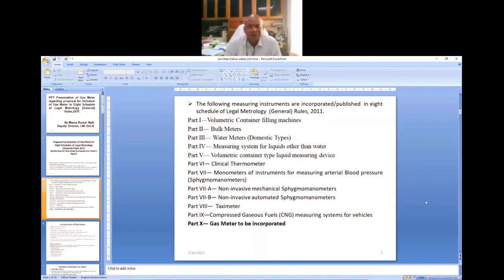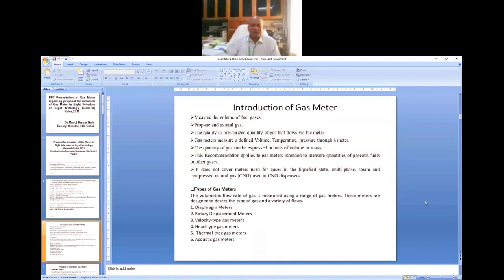It is proposed on the basis of OIML recommendation number R137 part 1 and part 2, edition 2012, and this is the proposed draft rules for the gas meter. A gas meter is an instrument intended to measure, memorize and display the quantity of gas passing the flow sensor. For propane and natural gas, it measures the quantity of pressurized gas that flows via the meter. Gas meters measure a defined volume under certain temperature and pressure through a meter. The quantity of gas can be expressed in units of volume or mass.